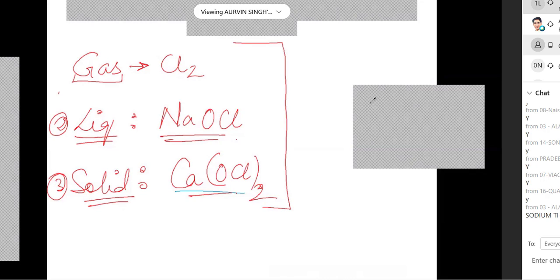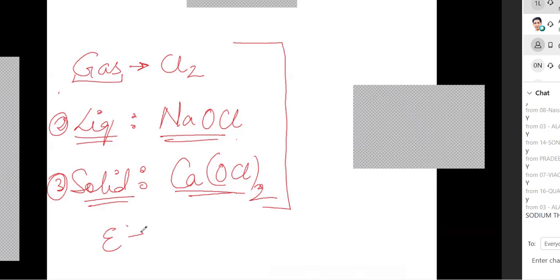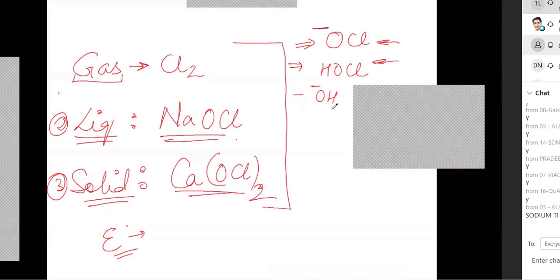Okay. But how do they work? See, ultimately, any of the chlorine you are dosing, whether you are dosing it as a chemical or generating chlorine in electrochlorination by passing electrical current, any of this chlorine ultimately is using these dangerous ions. One is your OCl ion, and secondly the acid which is called HOCl, hypochlorous acid, and hypochlorite ions. And in some cases hydroxide also, but that is for electrochlorination purposes. The first two, OCl minus and HOCl, are basically the chemicals that are killing the organisms, because they will attach to the proteins on the cell membrane and inside, and will change the protein qualitatively, it will damage the protein and the organism dies. This is how it works.